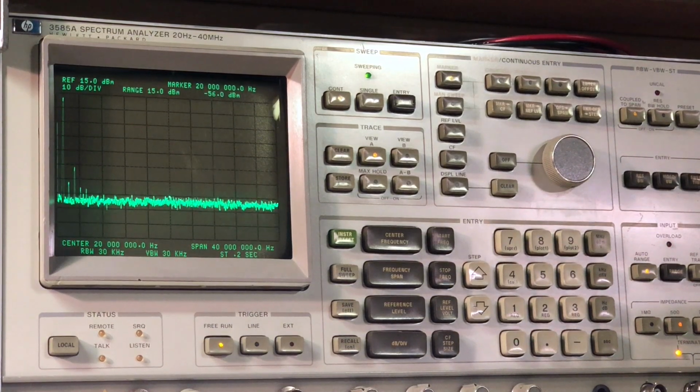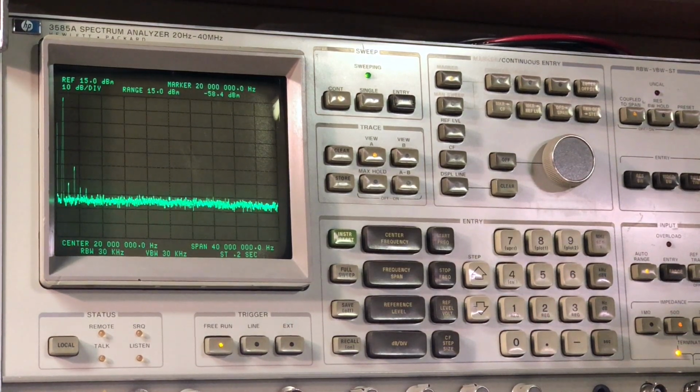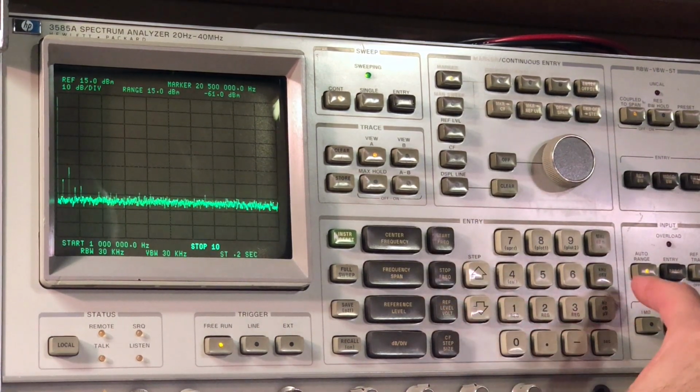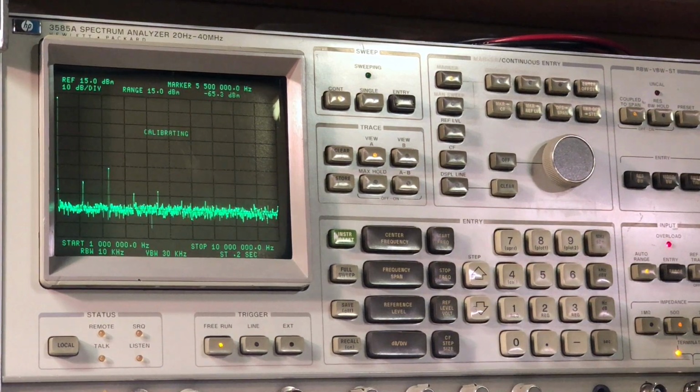So looking very good at this point. You can see the original harmonics we were looking at now are all scrunched over to the left-hand side of the display because the span is so wide at this point. So if I go to start frequency 1 megahertz, stop frequency 10 megahertz, puts us back how we were originally. So looking very good at this point. The output is very stable, the frequency is very accurate. The amplitude is really spot on, no problems with those values and readings and how the instrument is performing at this point. So the DS340 is ready to put back in service and is functioning correctly.